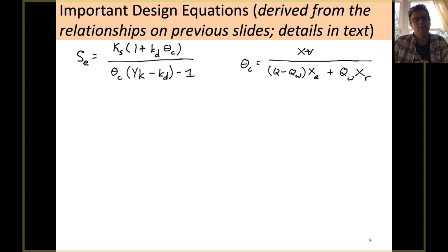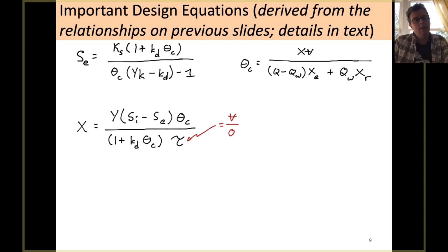Our solids residence time, our SRT, we saw this just a few slides ago, but again here in summary, that becomes a critical value for us. And X, and again that's the concentration of biomass in the aeration basin, that's something that's going to be of particular interest to us. In general, X is something that we might specify so that we'll know about the concentration of biomass we'd like to maintain. We don't want too much to get into this overcrowding problem. We don't want too little because it would be inefficient.